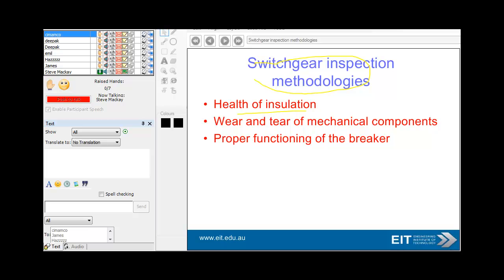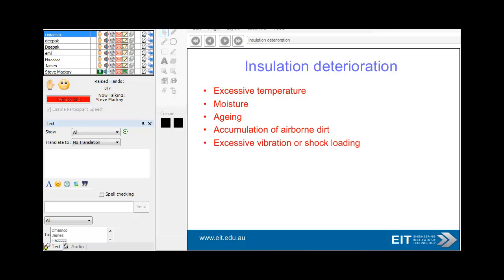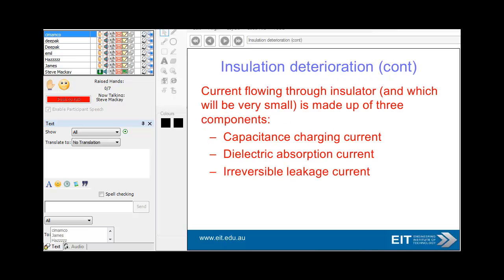Switchgear inspection methodologies: look at the health of insulation, wear and tear on mechanical components, and obviously the proper functioning of the breaker. Insulation deterioration is often due to excessive temperature, moisture, and of course inevitable aging. Accumulation of airborne dirt and excessive vibration are also factors. The components of the current include capacitance, dielectric absorption, and leakage current.